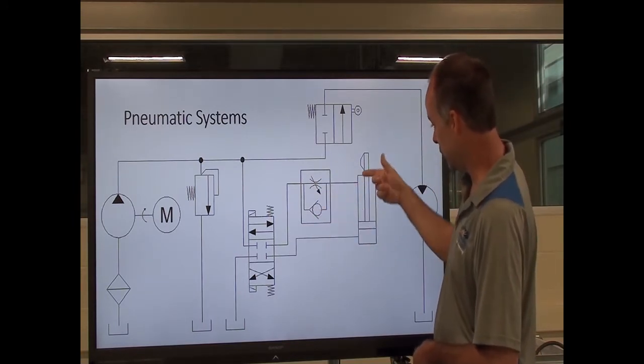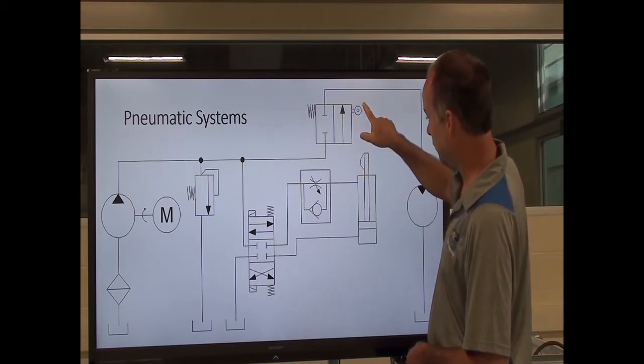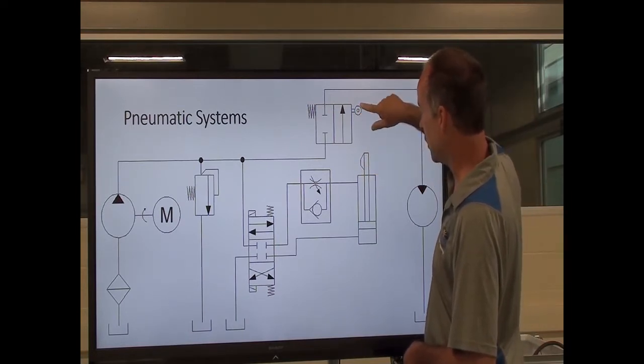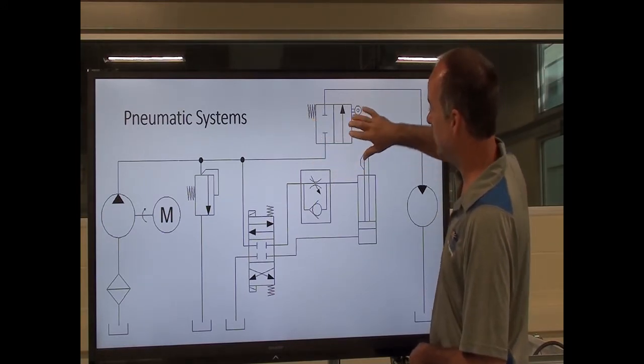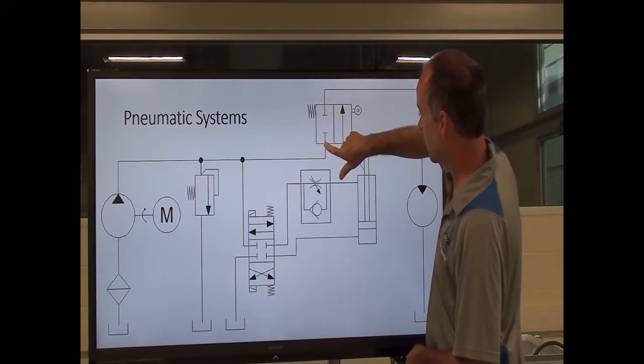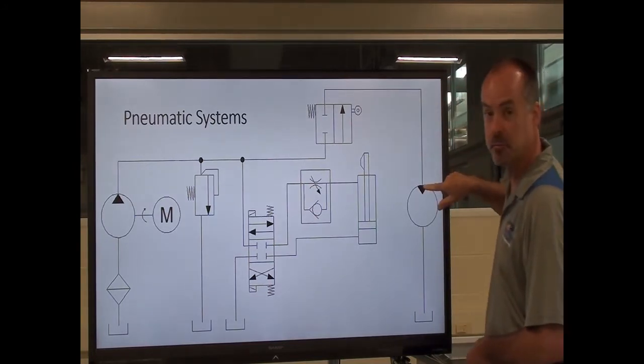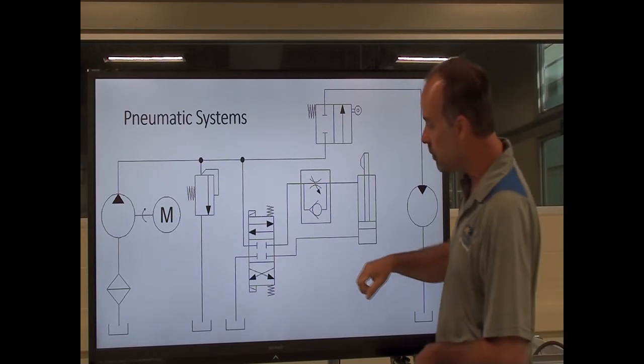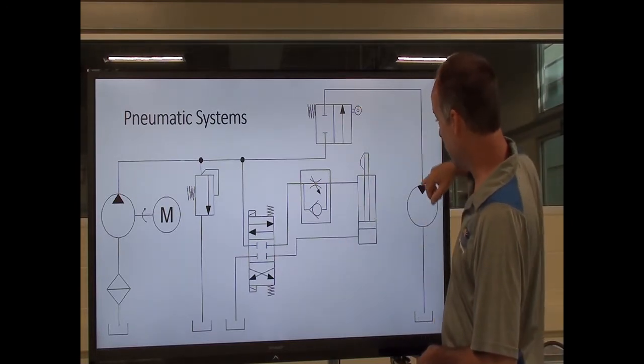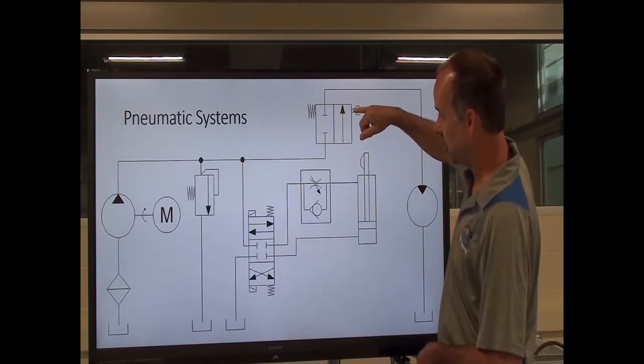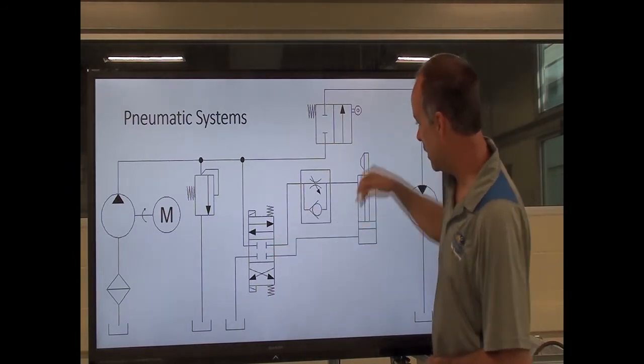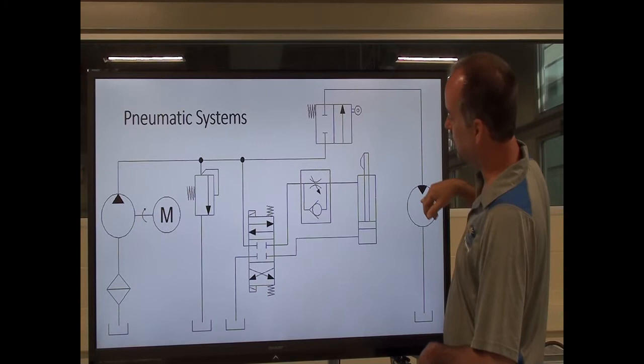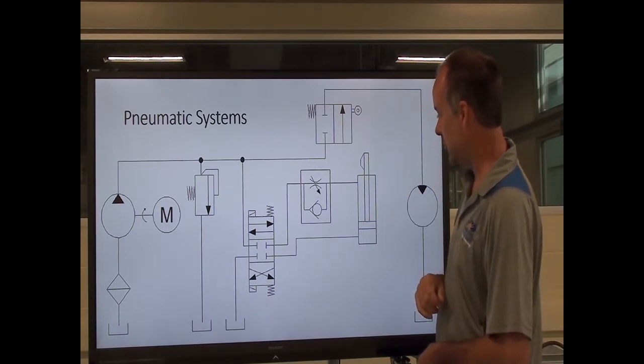This meter-out setup controls the extend speed, which is typically less than full speed. Once the cylinder extends all the way, there's a cam on the end of the cylinder rod that operates this cam operator. That shifts my two-way, two-position valve to allow fluid to flow from this port to this port, allowing my motor to run only when the cylinder is fully extended. The motor continues to run as long as the cylinder is extended and operating the cam valve. If we shift back and retract the cylinder, as soon as it comes off the cam valve, the valve shifts back, blocking the port and stopping the motor, allowing the cylinder to retract fully at full speed.